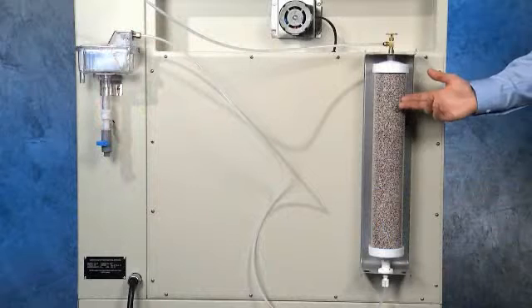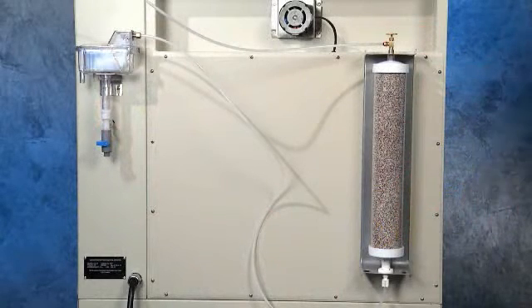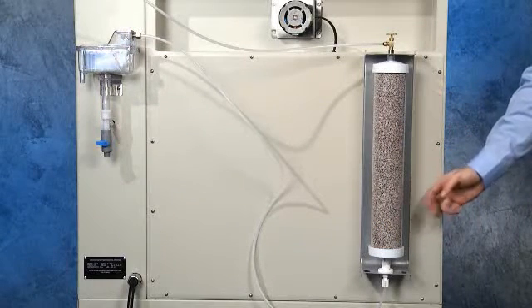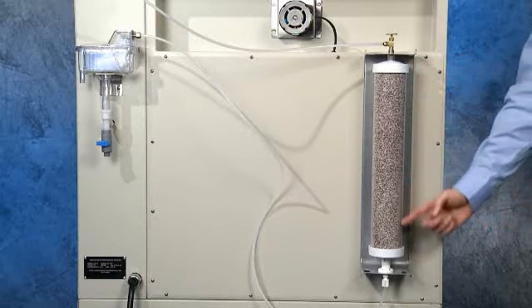The water demineralizer system consists of the demineralizer bracket, the deionizer filter, and the polytube water connections. The demineralizer bracket is factory mounted to the exterior of the chamber and allows for easy filter installation. The deionizer filter sits inside the bracket and is held in place by an upper pressure fitting and a lower receiving block.